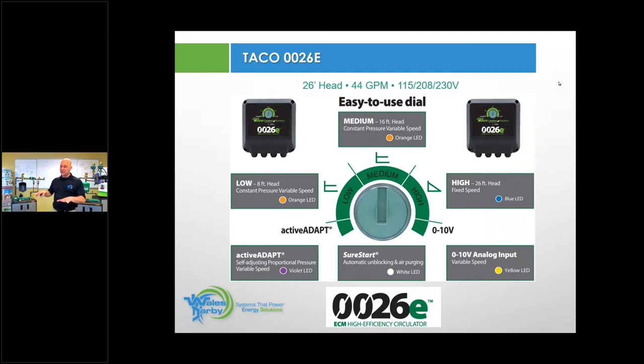All of these E-series circulators that we've shown you today only need two wires. No ground required. So if you're working in an older home and there's only two wires available, these motors are double insulated. We do not need a ground for the E-series circulators that we offer. So low, medium, high, you can even do a 0-10 volt signal. So a lot of different opportunities here with these ECM circulators.